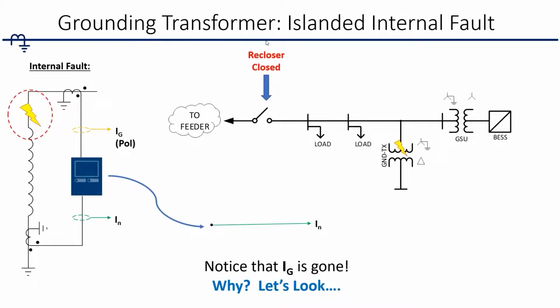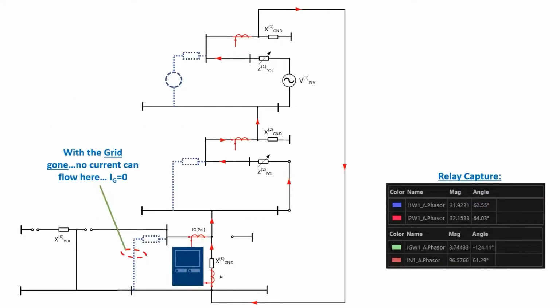So we opened up the recloser, islanded the system, allowed it to stabilize, and then placed an internal fault inside of the transformer. And you'll notice now that IG is gone. So why is that? Why is it that when we're islanded, IG is gone? We only have IN, which is interesting because we said that the REF operates off of an angular comparison. So what happened? What do we do now? There's nothing really to compare an angle to. So what does the REF protection do?